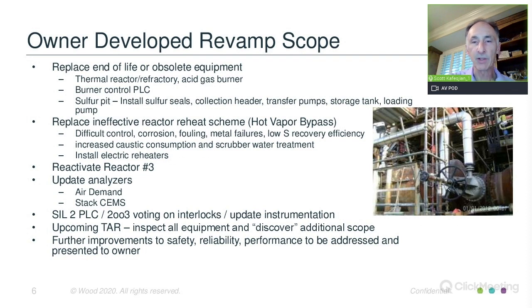This very complicated looking valve takes 2,000 degree F gas and splits it off to the reactors for reheating. This is a difficult service, and this valve had to be replaced every 1 to 2 years due to failure. The low performance also results in increased caustic consumption in the SO2 scrubber and increased blowdown water. And instead of the hot vapor bypass, the client wanted to install electric reheaters. They also wanted to put the third Claus reactor back in service. It had been out of service for many years due to operating difficulties. Update the critical air demand analyzer and the stack emission analyzer.